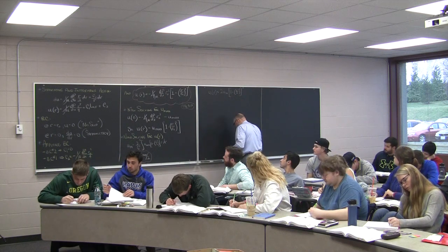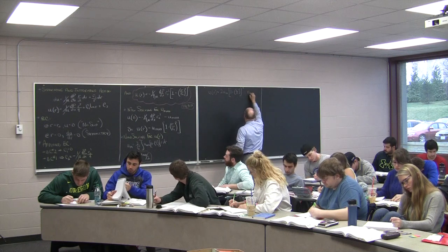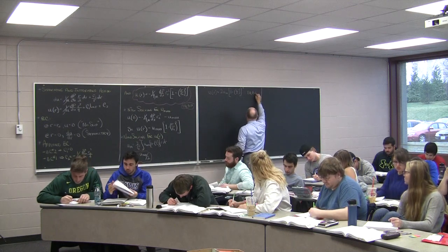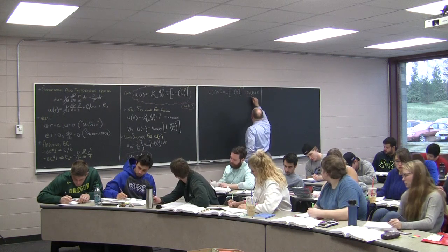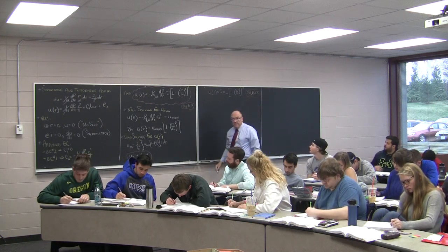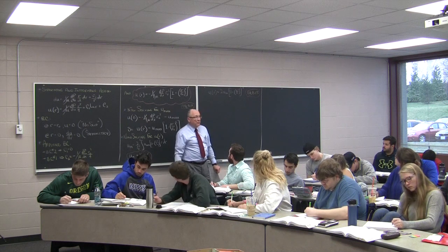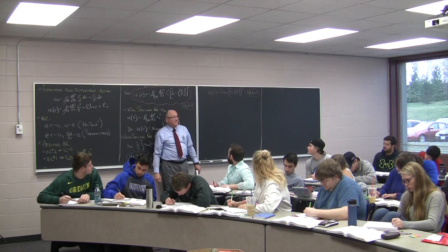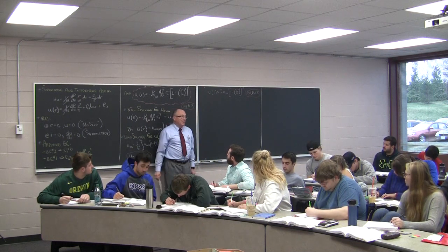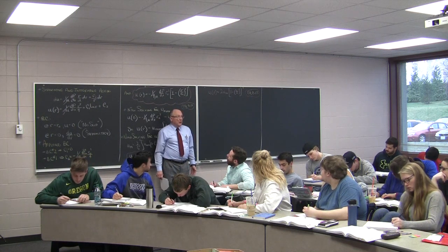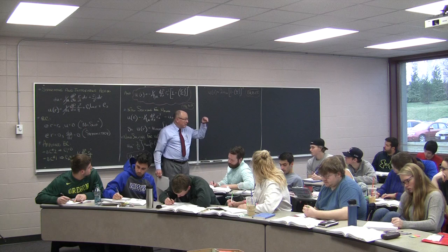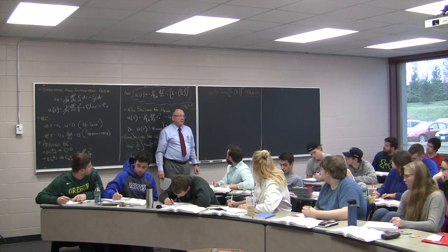And this is equation 8.15. Where do you think we measure when we stick a sensor into a pipe? Where do we measure the velocity? U max at r0, and you divide by 2. All right. So your mean velocity. That's typically where we measure when we put a sensor into a pipe.